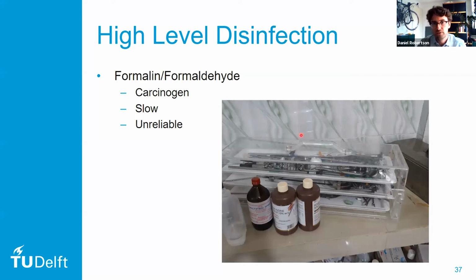The formaldehyde is released by tablets that are wrapped in gauze pieces, and they release the formaldehyde gas in these types of boxes. Now, formaldehyde gas has absolutely no advantages for use, and if you can, I would stop using these boxes as soon as possible. This is because it's very, very difficult to reliably operate formaldehyde sterilization and disinfection. The gas is only effective under specific conditions. So, for instance, we need an 80% room humidity inside of the box to achieve sterilization with formaldehyde.